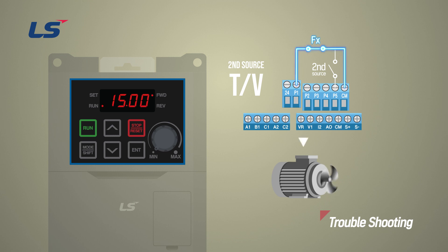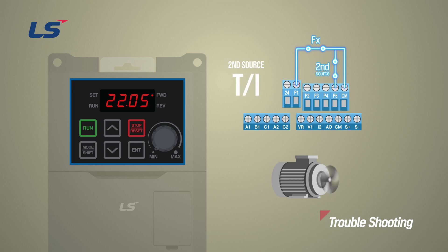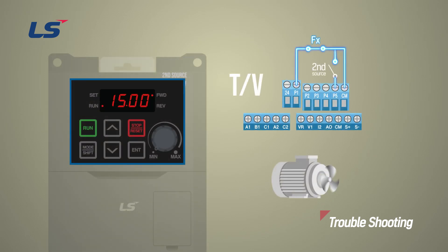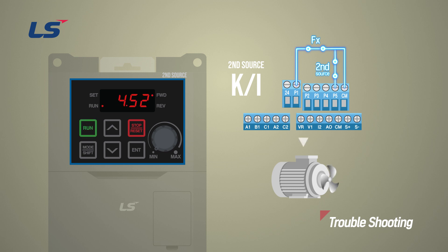If the second operation is terminal command, the operation will continue as the operation command is identical to the original operation and only the frequency source is changed. But if the command source is also changed, the operation will be stopped. The operation will resume once the changed command source is enabled.